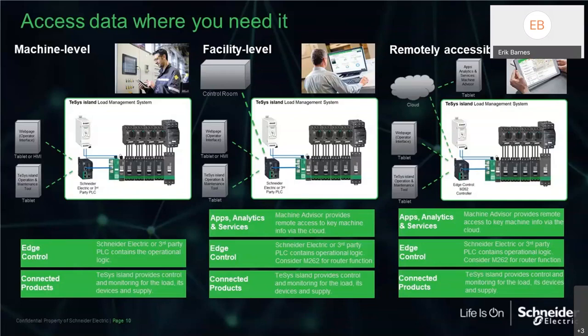In some cases, you can actually manage the issue through the PLC. For example, if you have a pump application and it's detecting a jam, you may want to program your PLC, when it gets the jam alarm, to initiate a reverse, right? And try to clear it without having to even bother the maintenance technician or the operator. And only pull them in if you've tried three times and it didn't work, right? So there's a lot of things you can do to make it easier for the customer. They may not even need to know there was an issue. They could just get a report that says, hey, we found this issue, we took care of it, right? That's a very huge value add for equipment manufacturers or equipment purchasers.